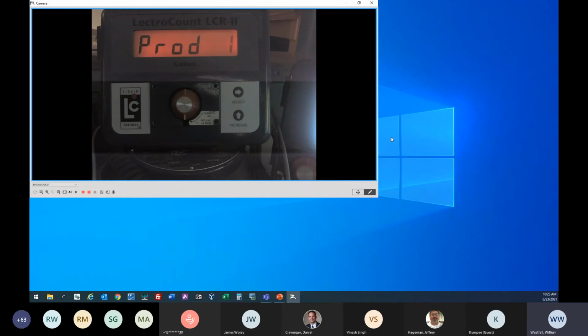So if you are calibrating more than one product and they don't have a default K factor in there, you will absolutely need either EZCommand or a lap pad in order to set a default K factor in those products. Once you have a default K factor in their pulses per unit, then you'll be able to cycle through the different products using the increase button.